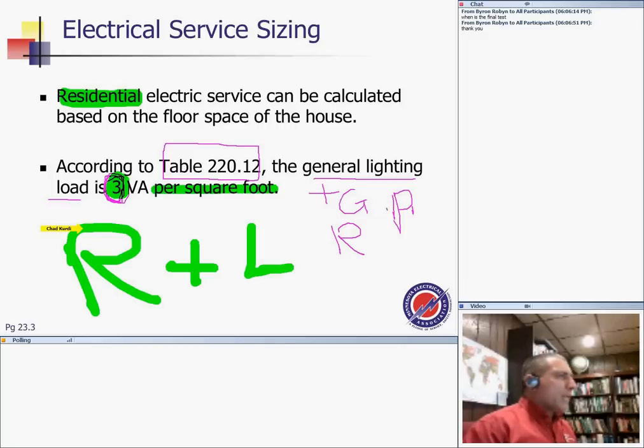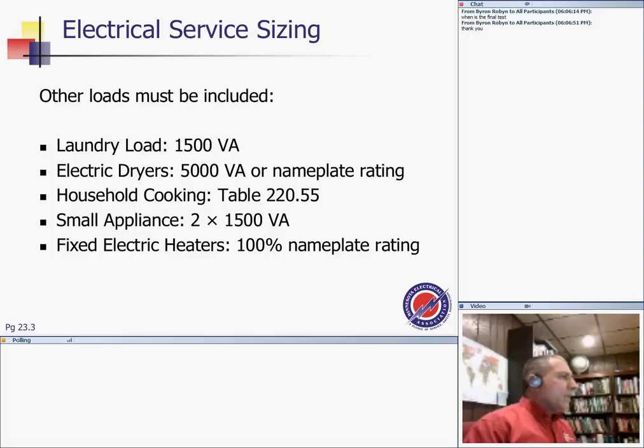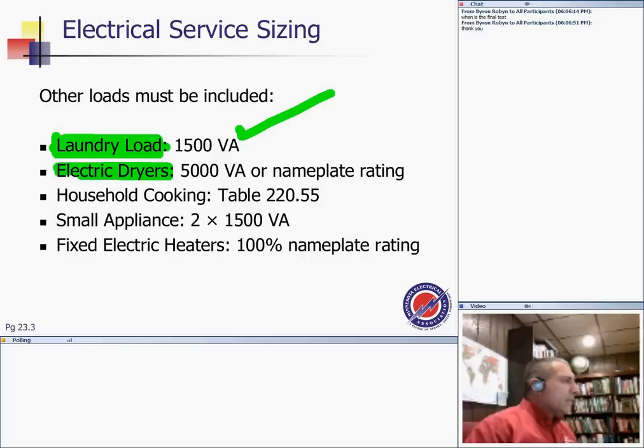First thing is 3 volt amp, and I'll show you how the calculation goes, guys. The second thing, so 3 for general purpose receptacles and lights, so you take 3 volt amp multiplied by the square foot of the building, and that will give you how many volt amps you need for this apartment building or this house. The second thing, based on code, the laundry. The assumption is if you have a laundry, you always need 1500 volt amp for your laundry circuit. If you have an electrical dryer, gas dryers don't include that. If you have an electrical dryer, it's always 5000 volt amp or nameplate, whichever is larger. Very important. Cooking equipment, we have table 220.55, and I have an example that we go through on that one.